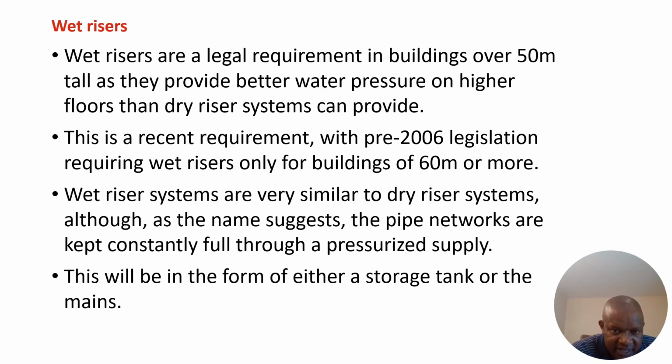Wet risers, on the other hand, are a legal requirement in buildings over 50 meters tall. They provide better water pressure on higher floors than dry risers can provide. This is a recent requirement, with pre-2006 legislation requiring wet risers only for buildings of 60 meters or more.